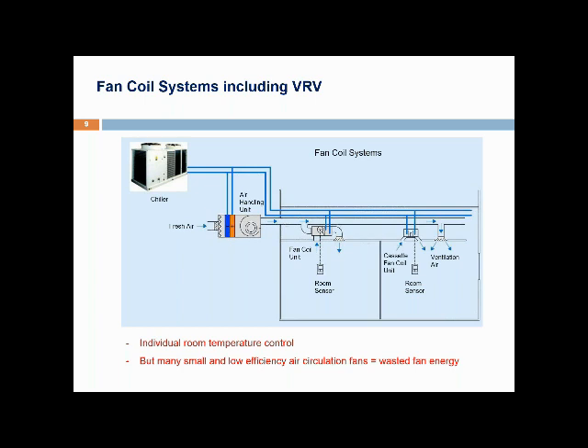Fan coil systems — whether chilled water fan coil or fan coils using refrigerant like VRF — operate similarly: one uses chilled water and the other uses refrigerant to distribute and vary the amount of cooling supplied to the space. They both provide individual room control, but they have a disadvantage: many small terminal units with many small recirculation fans operating at very low efficiencies, which results in wasted fan energy.